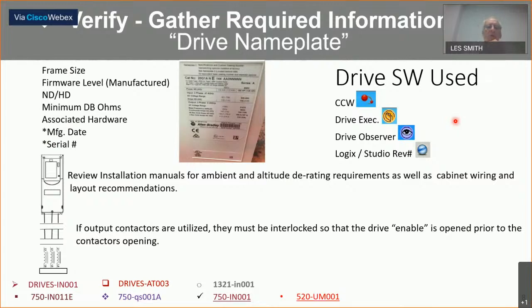But what I looked at here was to gather required information, being aware of what you have in front of you. We take a look: the nameplate on a drive will tell you the frame size. The frame size will relate to options available relative to that frame size. Firmware level will tell us when that drive was commissioned, and if we want to accept that firmware level or flash it back in case of replacement.